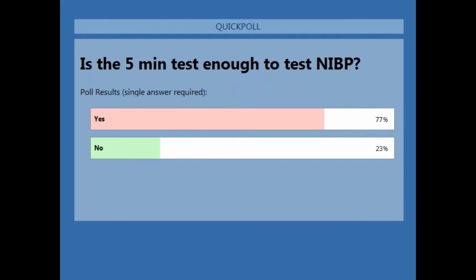Accuracy requires that we do static pressure comparisons, and in order to do that, we have to be in the service mode of the patient monitor and in the NIBP section to verify several things, including accuracy. So when we get into that service mode, then it's important for us to first do a leak check on the NIBP system to make sure that it can hold pressure within reason. Now, every pneumatic system has a little leak, so we just want to make sure that the leak rate is within acceptable tolerances.